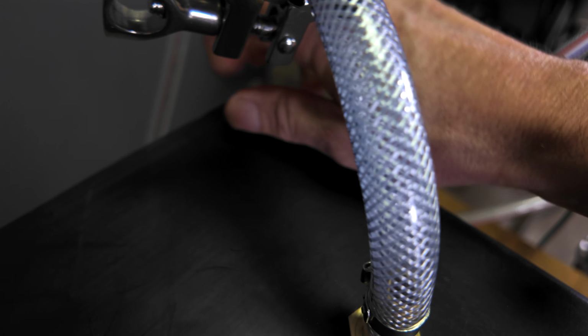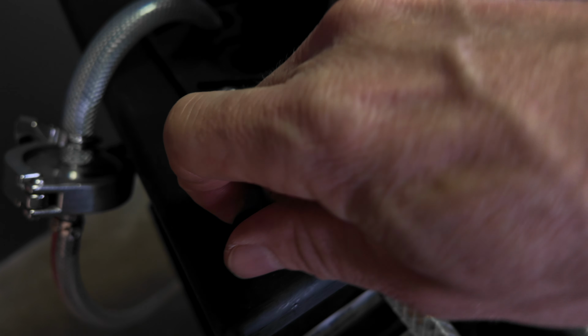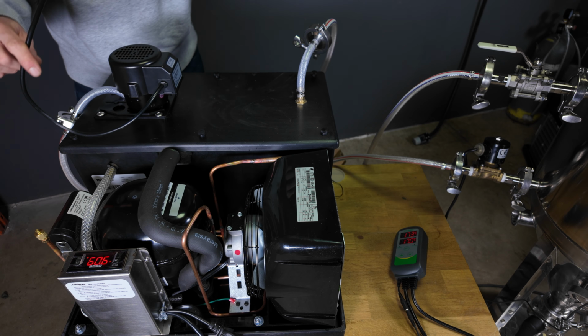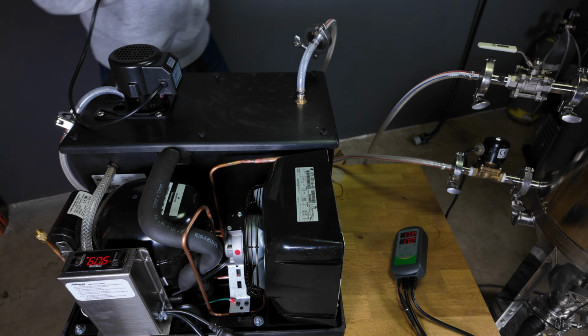You can mix it directly in the tank or pre-mix it in a separate container if you prefer. Once filled, make sure the reservoir is at the proper level before starting the system. And before turning the chiller on, confirm that all of your lines are connected and free of kinks so you get proper circulation. The chiller is designed so its internal controller can run the pump directly.